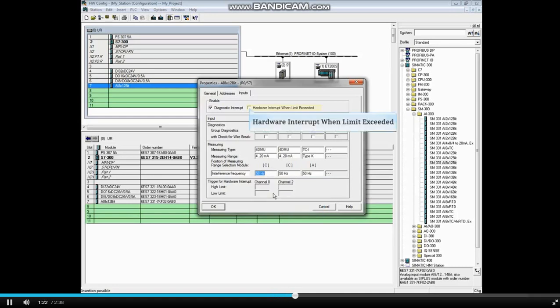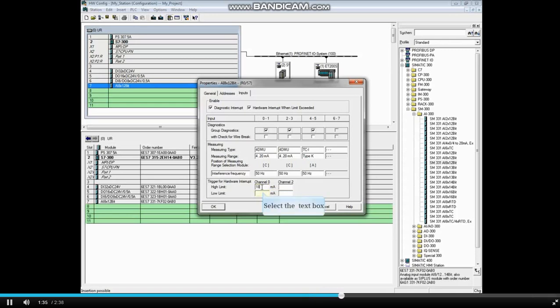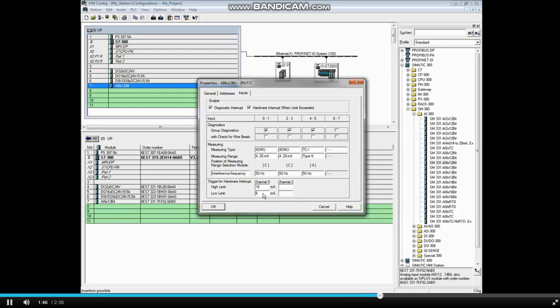The checkbox Hardware Interrupt When Limit Exceeded allows you to set a high limit and low limit range for channel 0 and channel 2. If we were to set the high limit at 18 milliamps and the low limit at 6 milliamps, then if the signal goes below 6 milliamps or above 18 milliamps, the organization block OB40 will be called for. The user can program the desired action in OB40.